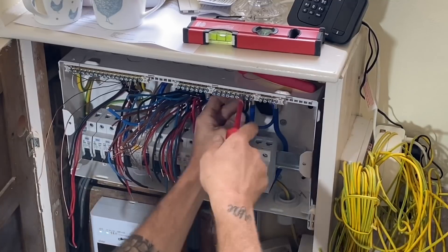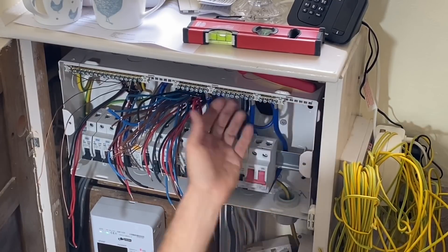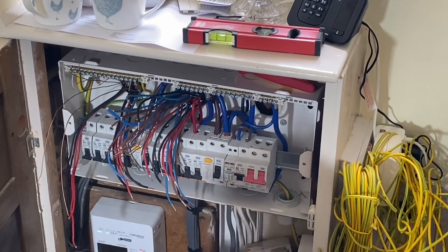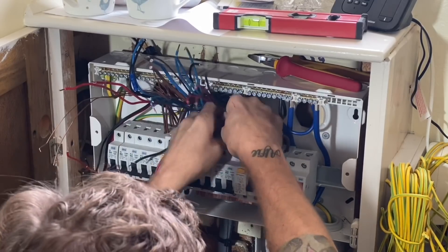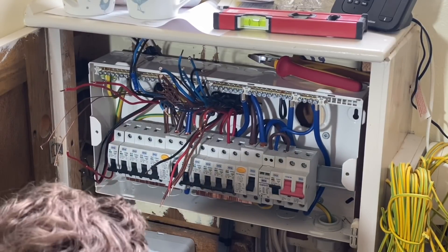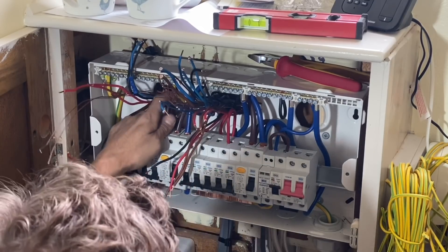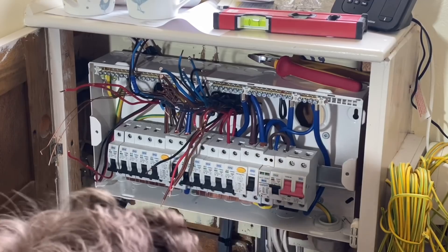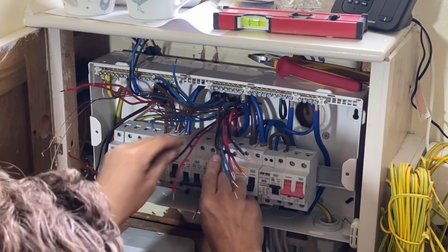Nice in with the screw — it's all set, just bend it in. I just find there's a lot of room to work in there. And all the screw heads are the same — plus/minus, or crosshead, whichever you want to say — so you could use one screwdriver for the whole board. We will be going back to the Torx screwdriver before anyone jumps in — we're just nipping them in at the moment. So with the way you dress the cables, I can see you taking the line conductors down the back where the DIN rail is — line first, then neutral or earth. Rather than sweeping your neutrals across with your CPCs, you give yourself the maximum amount of room, even though there's a huge amount of room behind there. That's just how I've always done it — otherwise I'll end up with a bird's nest, and the OCD in me just wants to scream.